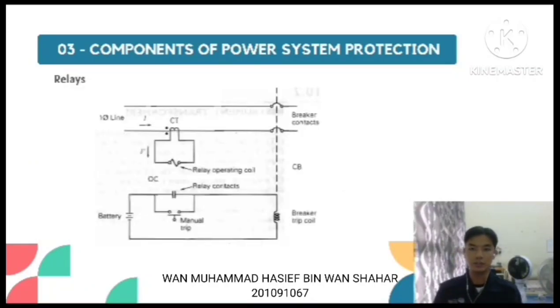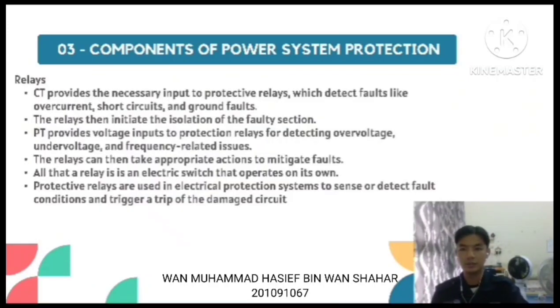Second, relays. The CT provides the necessary input to protective relays, which detect faults like overcurrent, short circuits and ground faults. The relays then initiate the isolation of the faulty section. The PT provides a voltage input to the protection relays for detecting overvoltage, undervoltage and frequency-related issues. The relays can then take appropriate action to mitigate faults.